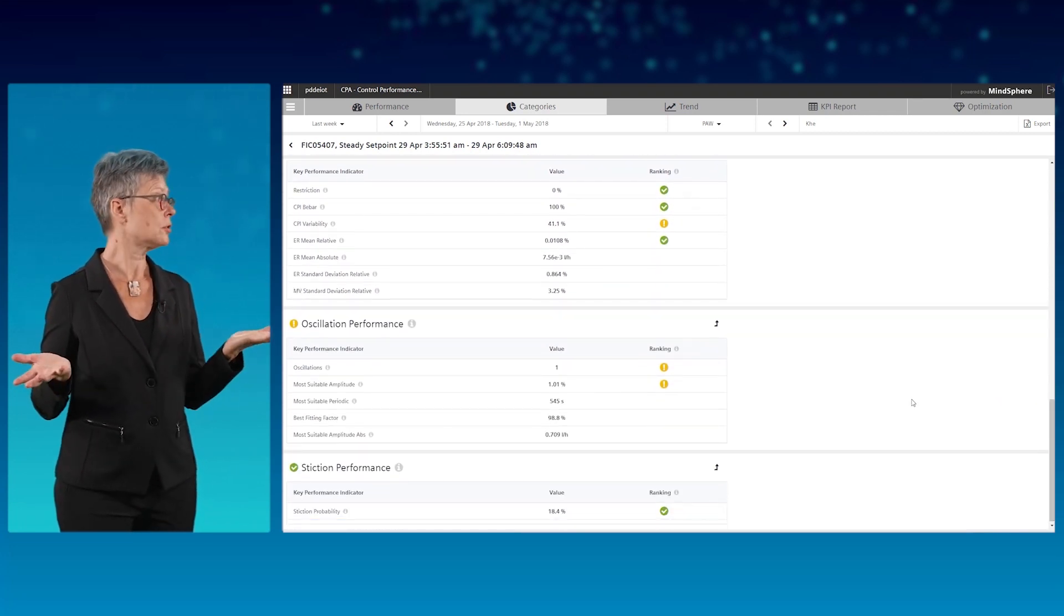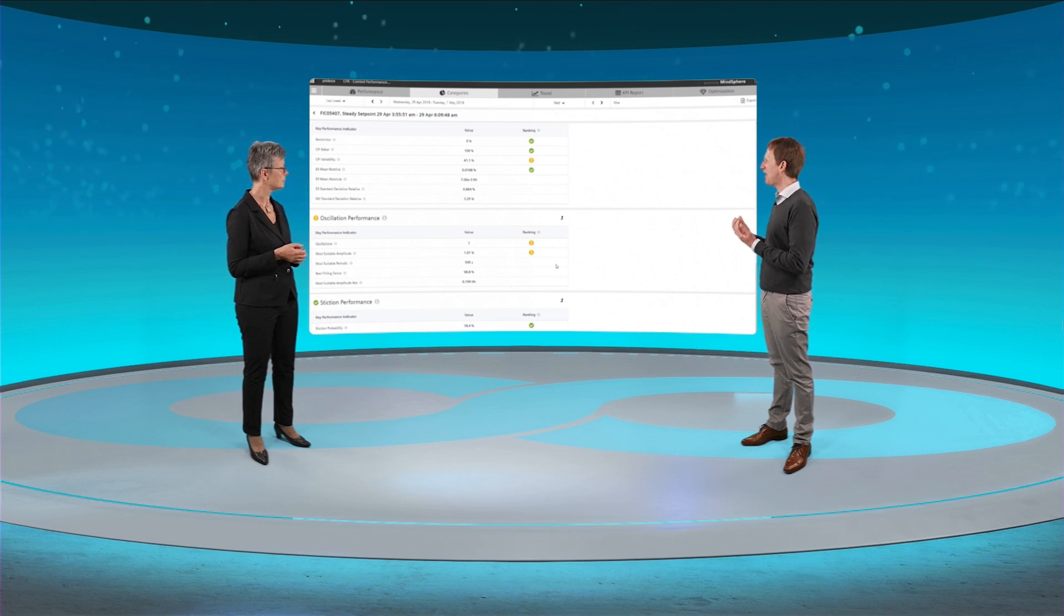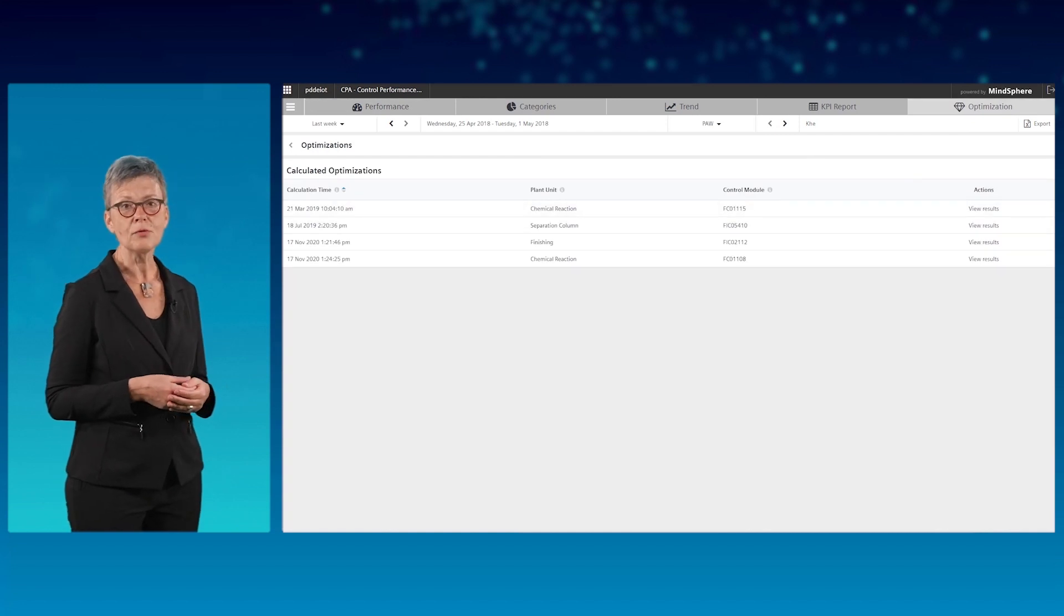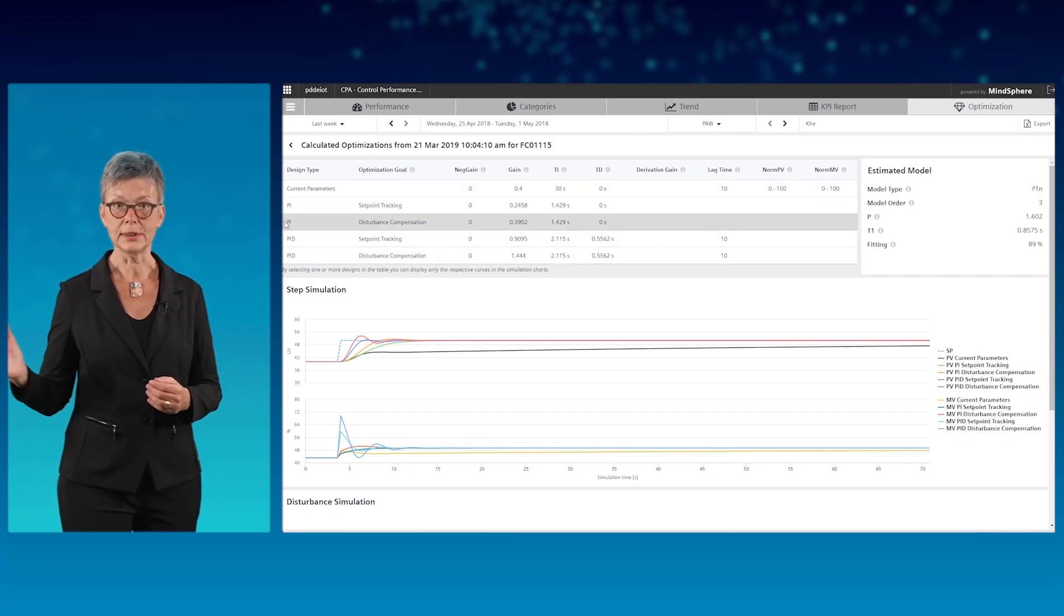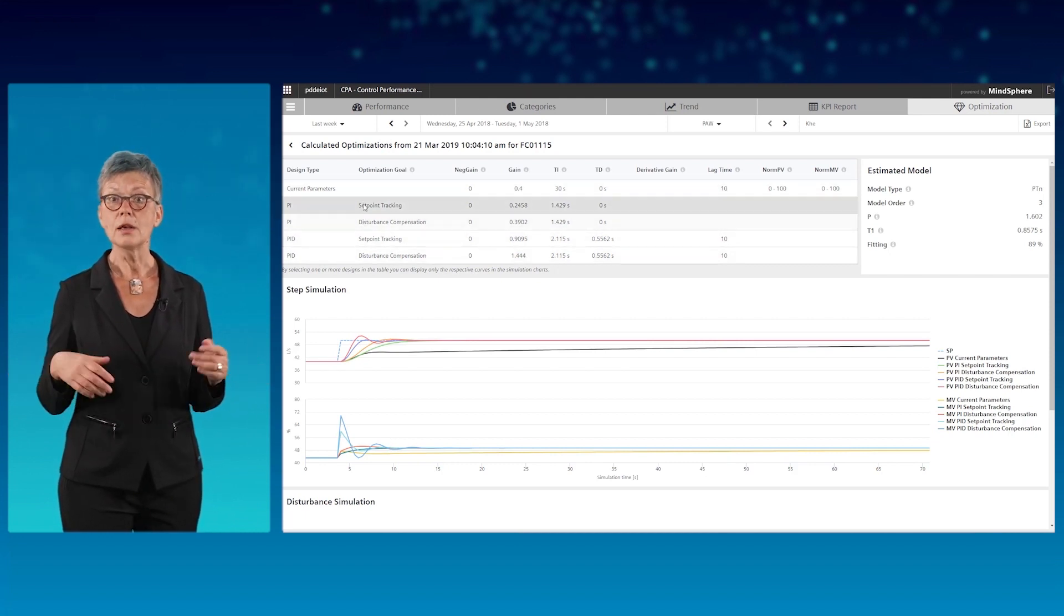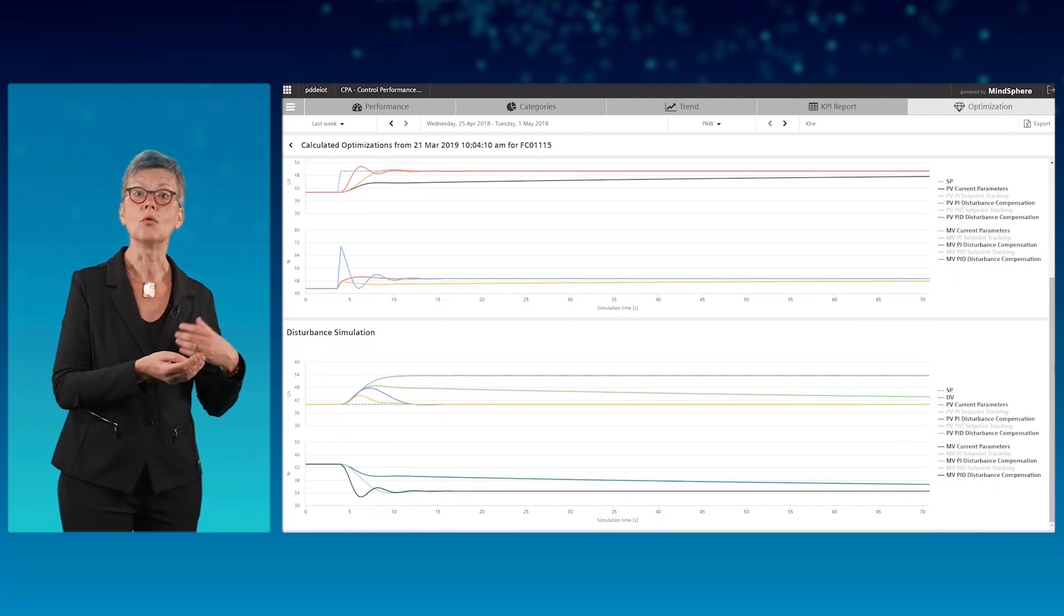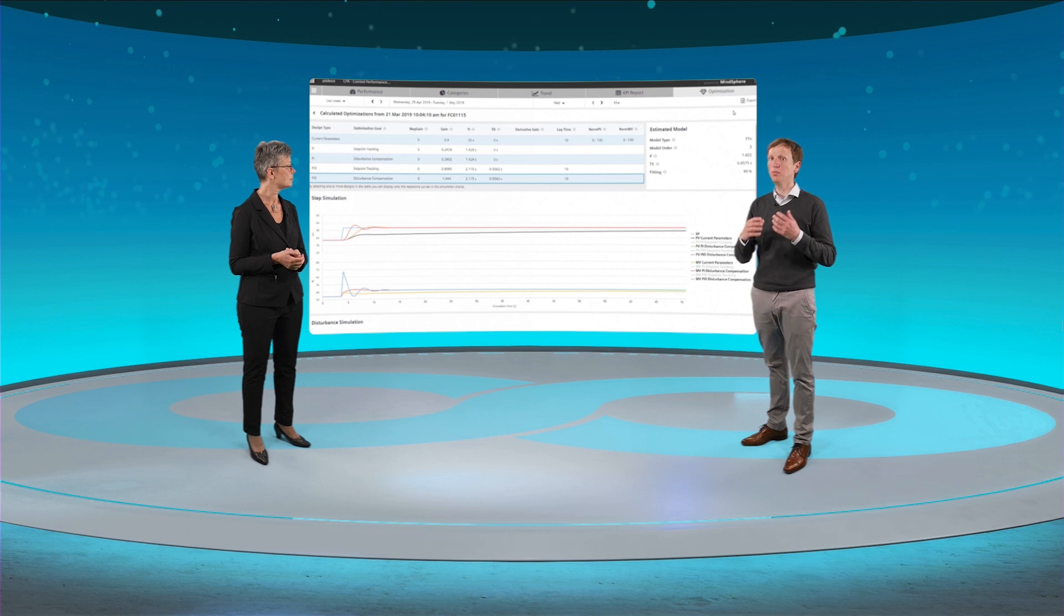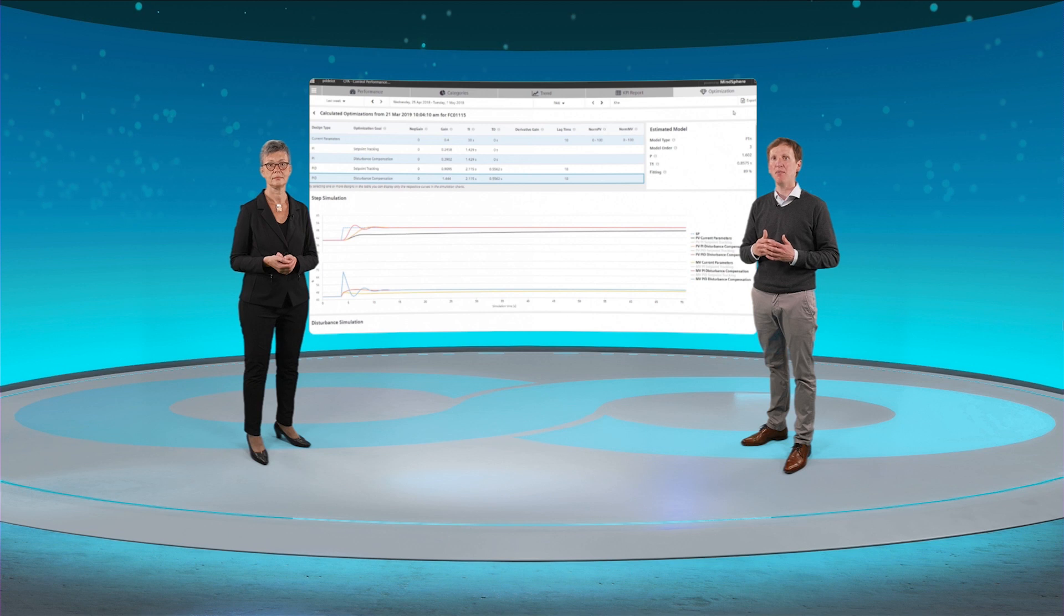Okay, so CPA basically does the performance monitoring of PID control loops for you. But then what? From my time as a project engineer, I recall that quite often there were loops that would have benefited from some tuning. Absolutely. If you are sure that the control loop needs retuning, you can have CPA do the calculations for you. CPA uses the available data and calculates optimized sets of PID parameters for different scenarios. Users can choose not only between PI and PID control, but also whether they prefer set point tracking or disturbance rejection as the main task of the loop. So, CPA provides transparency of control loop performance across the whole plant. It gives you insights as to what categories of problems might be there, and even provides optimization calculation for optimized PID parameters if needed.